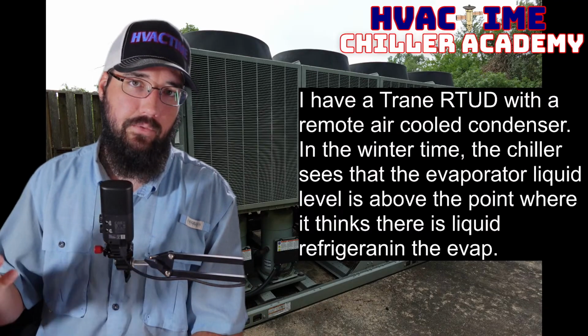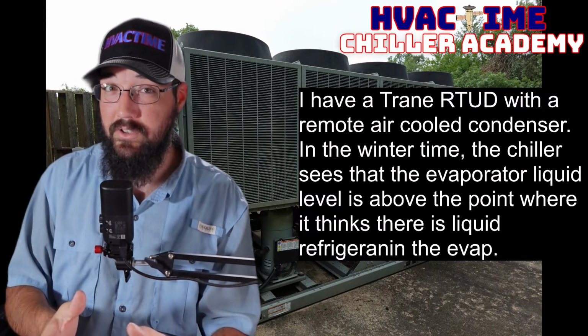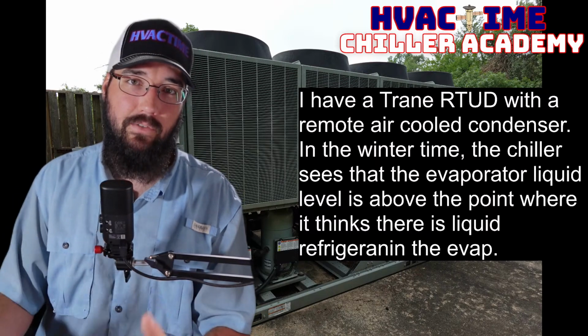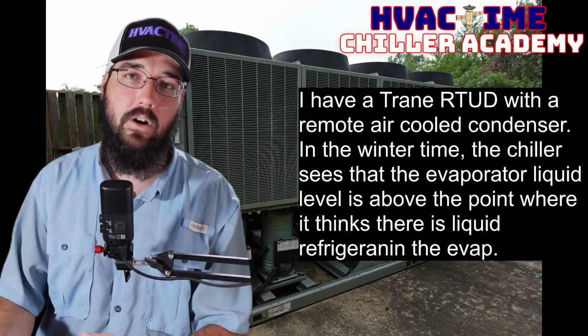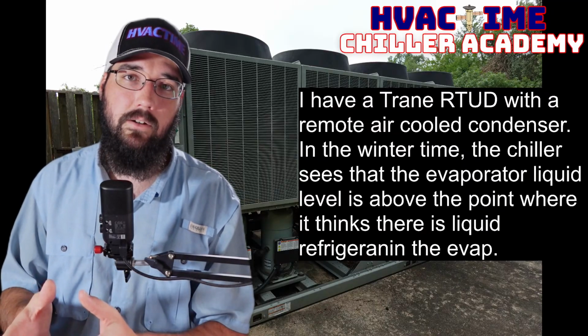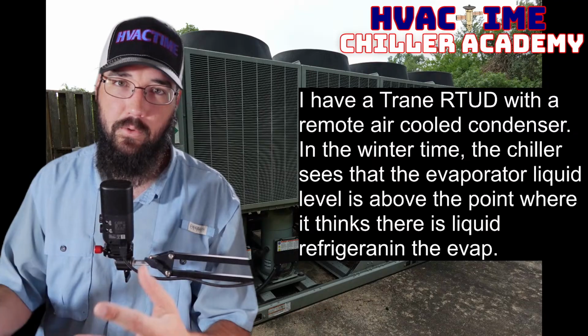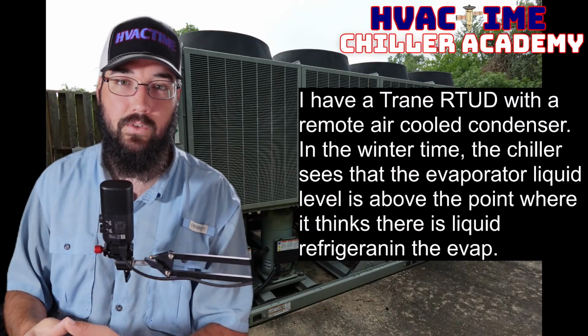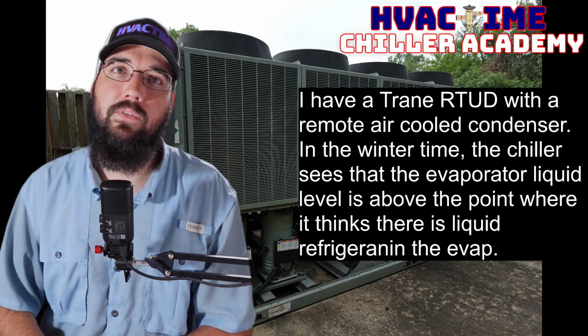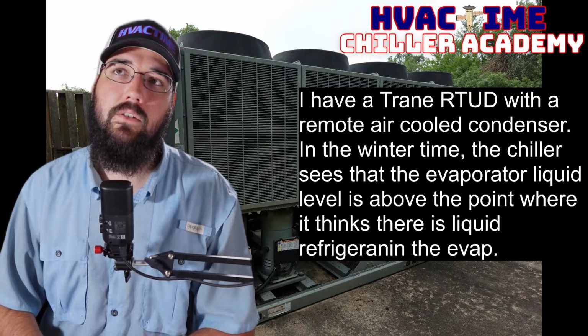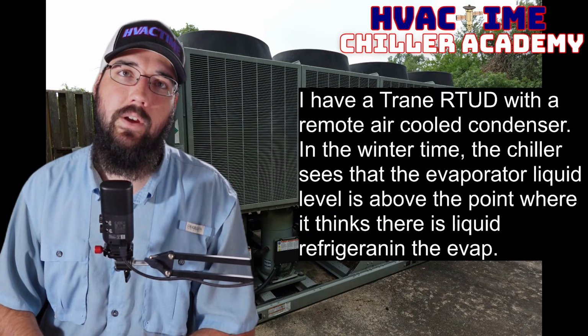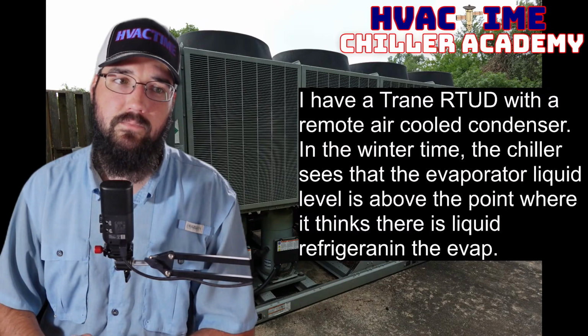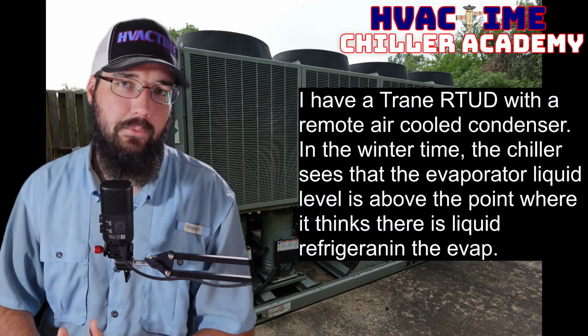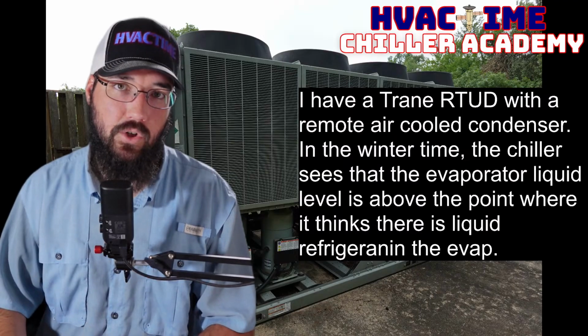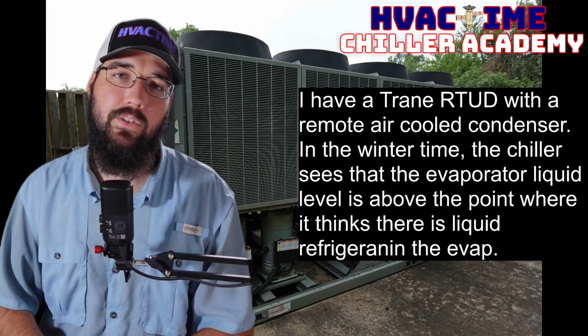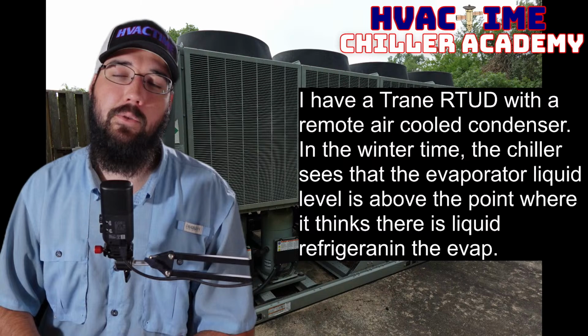Again, that check valve could be an issue. Maybe it's a combination of problems. Maybe that check valve is having a minor issue. Maybe you are having a low condenser head pressure problem. These things could be working in unison. Let's see, that oil return line should also have a filter on it. You need to make sure that filter is allowing proper flow and it's not needing to be serviced. When was the last time it was serviced?